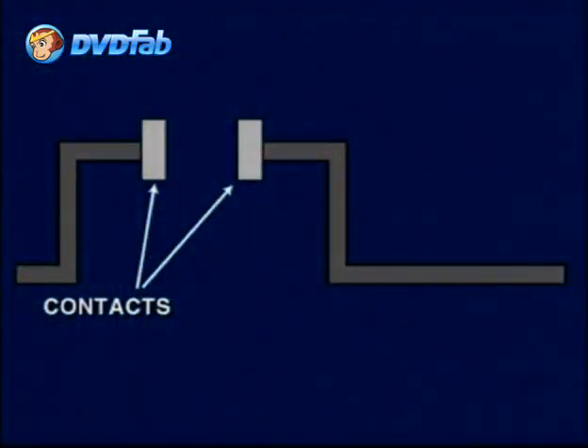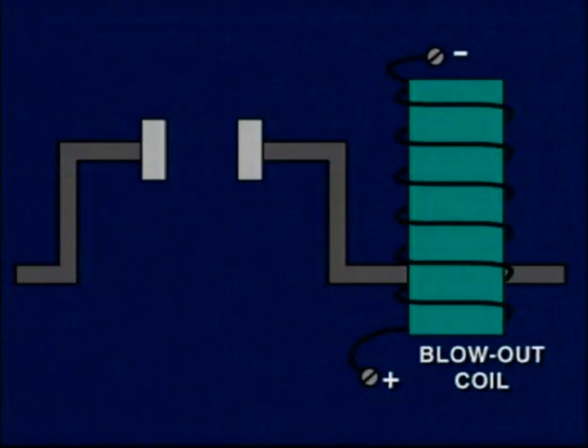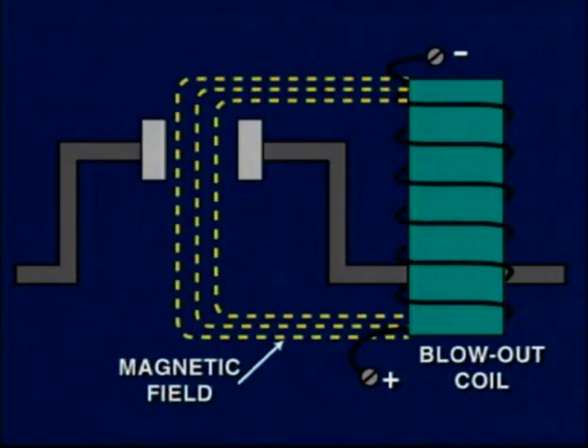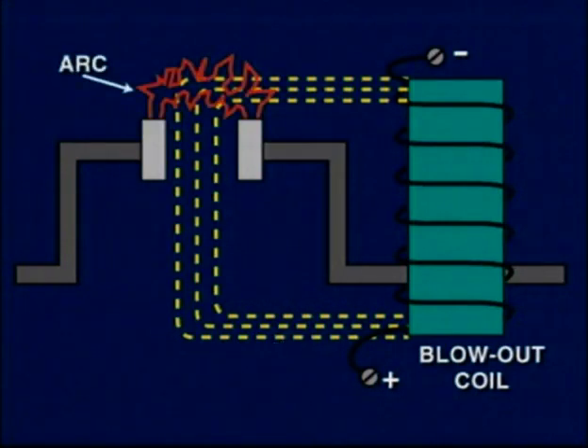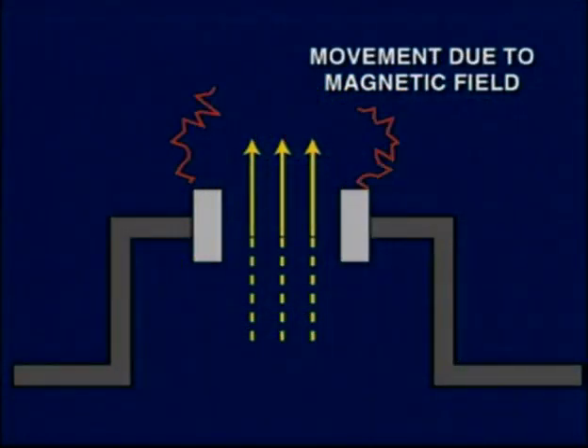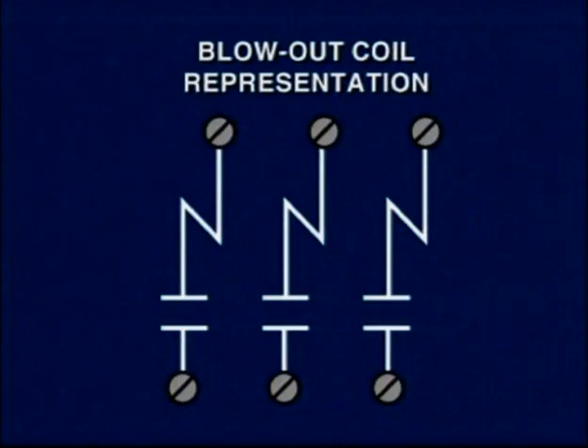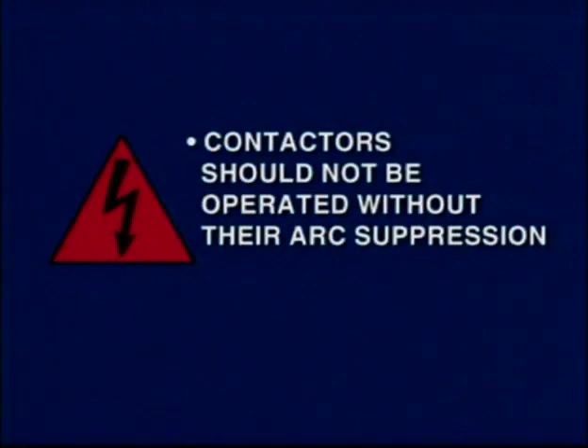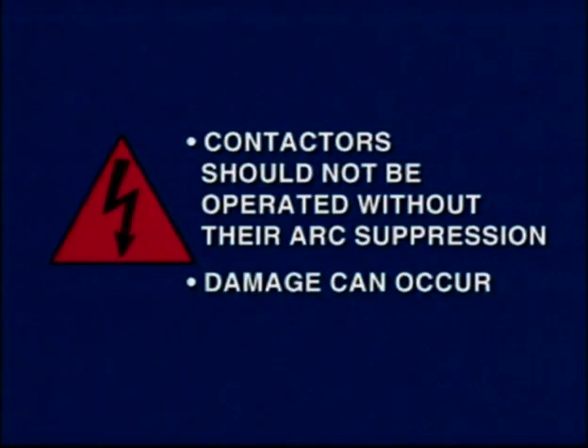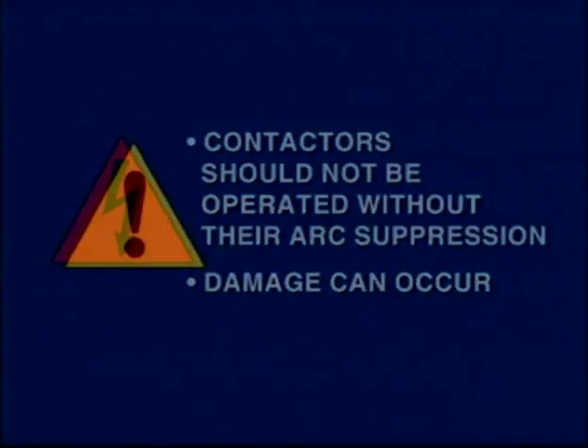Contactors may also provide a DC magnetic blowout coil for arc extinguishing. These blowout coils produce a magnetic field across the pole as current flows through the coil. This field interacts with the arc, pushing up or blowing out the arc into the arc chute, where it is enlarged and extinguished. When a contactor has blowout coils, its power contacts are represented by this symbol. It is important to note that contactors should not be operated without their arc suppression elements, because damage can occur to the contactor or to the machinery or loads it is connected to.